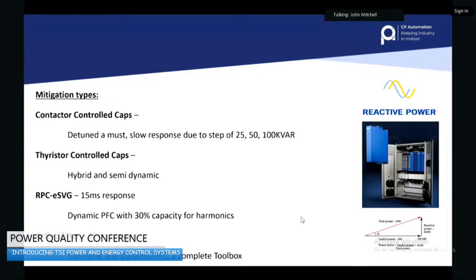The other way is to have things called detuned capacitor banks, where they've got chokes in front, and that is a real help. It eliminates most of the resonance issues, not all. And then there are some other modern technologies on the market today. So we offer a product called an ESVG, and this is an electronic way of handling power factor correction. It's using basically drive technology to improve it, and it's dynamic, so it doesn't wait for the steps to change and step up. It's instantly modifying the power factor on the fly.